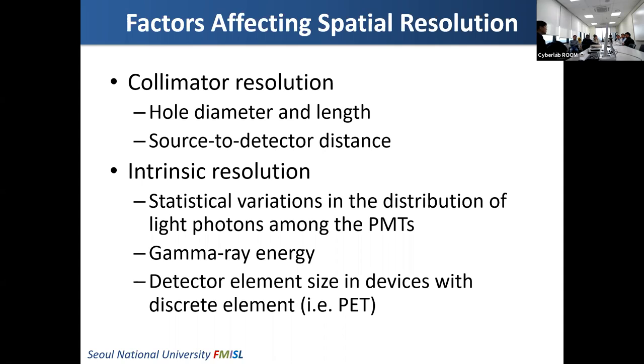In the previous lectures, I emphasized that collimator resolution is more dominant than intrinsic resolution in the SPECT system, so the system resolution is mainly determined by collimator resolution. The two factors that determine collimator resolution are the hole diameter, the hole length, and source-to-detector distance.